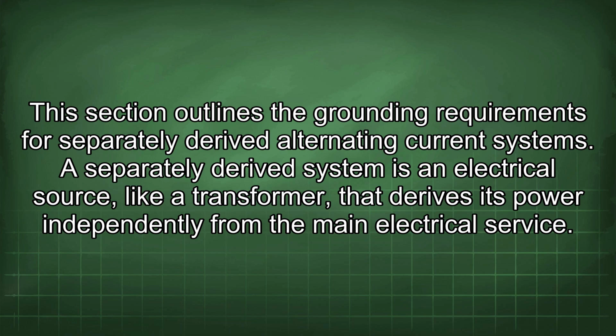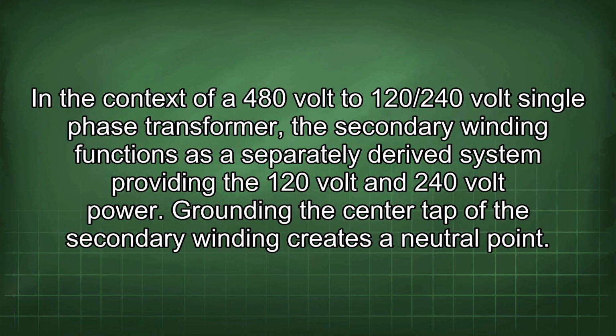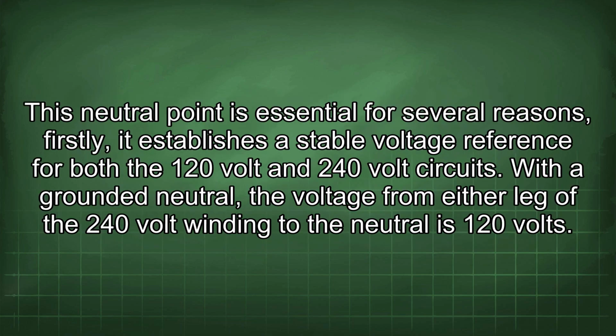A separately derived system is an electrical source, like a transformer, that derives its power independently from the main electrical service. In the context of a 480 volt to 120/240 volt single-phase transformer, the secondary winding functions as a separately derived system providing the 120 volt and 240 volt power. Grounding the center tap of the secondary winding creates a neutral point. This neutral point is essential for several reasons.